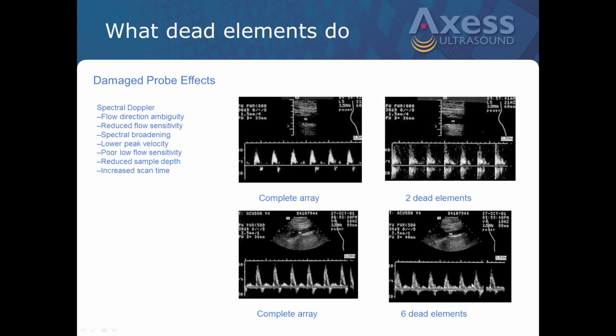Now here we're looking down in the abdomen. Again, we've got a normal Doppler flow. Over here, we've got six dead elements simulated in this same probe, and once again we've got a lot of turbulence. Where you should have a good, clear window in the Doppler spectrum, this shows that we have some turbulence, possibly some blockage. So I'd encourage you, at this stage, when you think you have dead elements in a probe but aren't really seeing anything in the 2D imaging, check the Doppler, because Doppler will bring these issues to the forefront as to whether the probe is providing true, good, positive clinical performance.